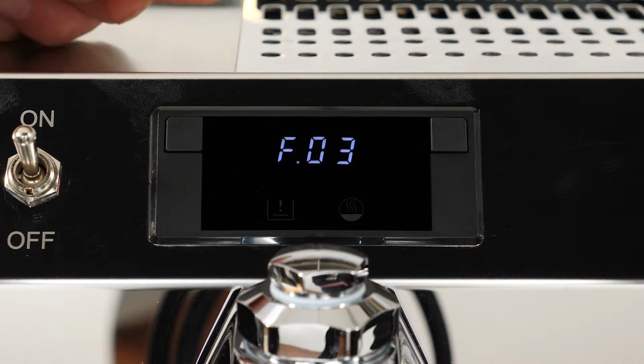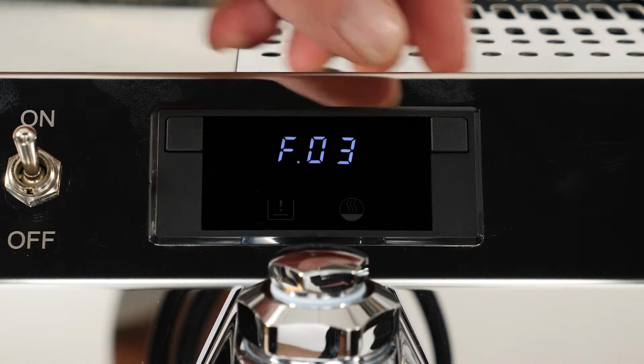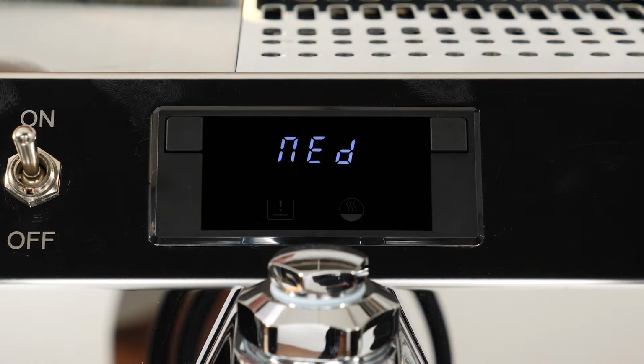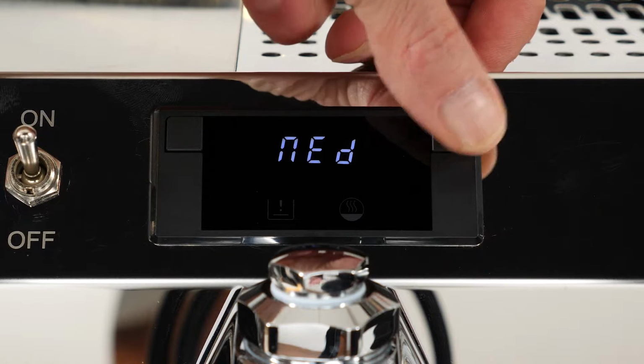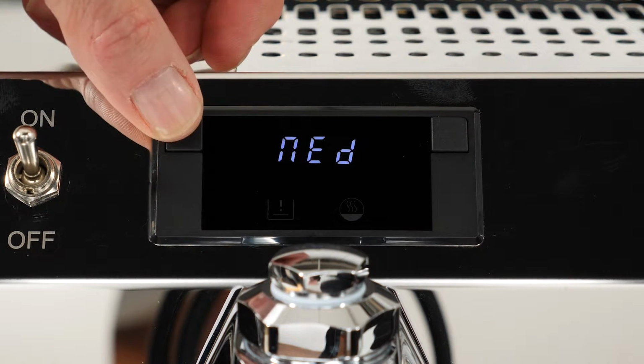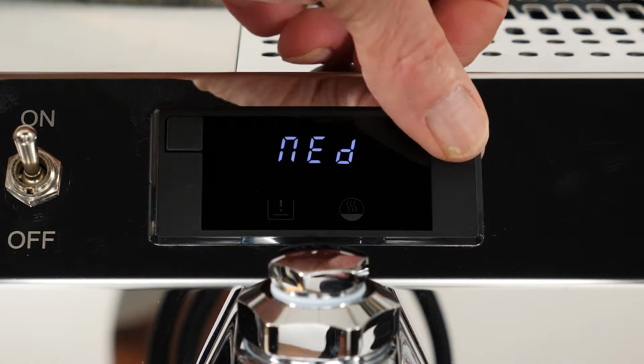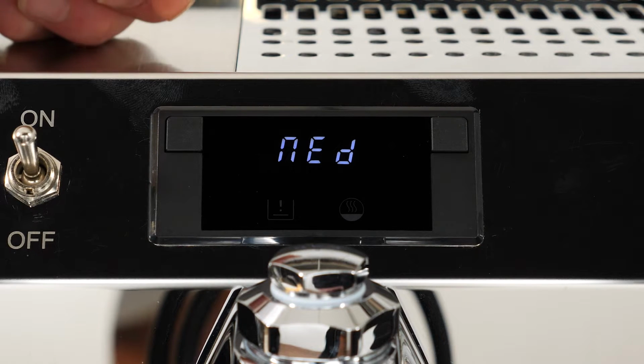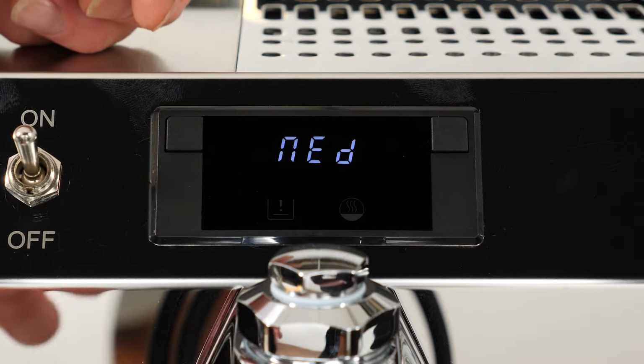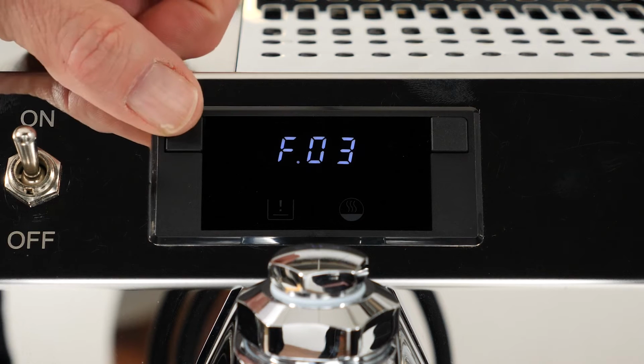Next, F03, our boiler probe sensitivity, comes set to medium. You can also do minimum or maximum. If you have really soft water, you may want to set it to max, but for most people, medium as it comes is perfect—it just increases the sensitivity so the probe knows there's water in there.